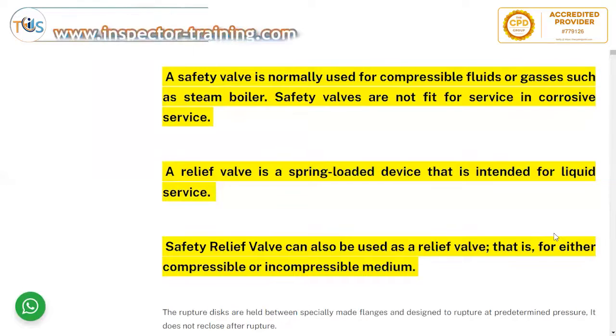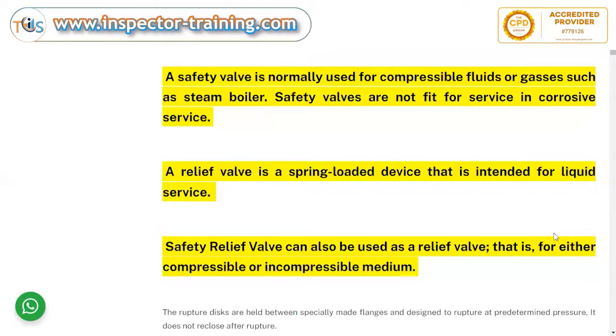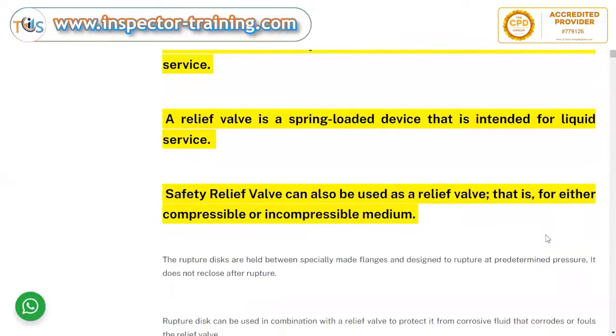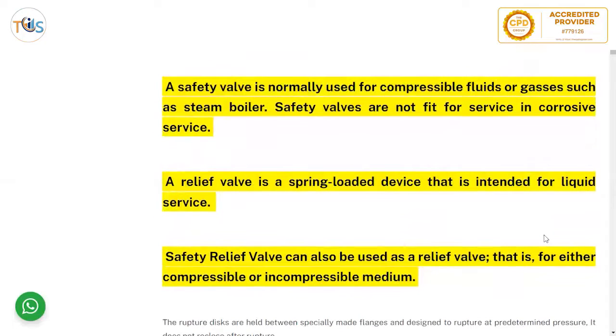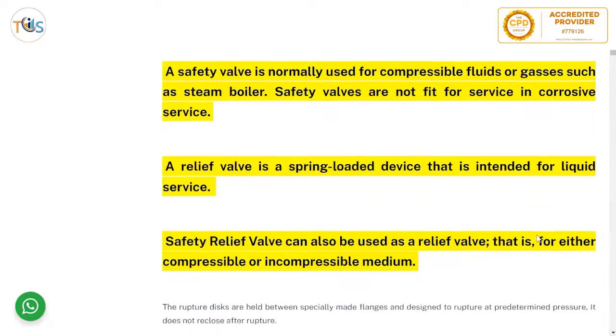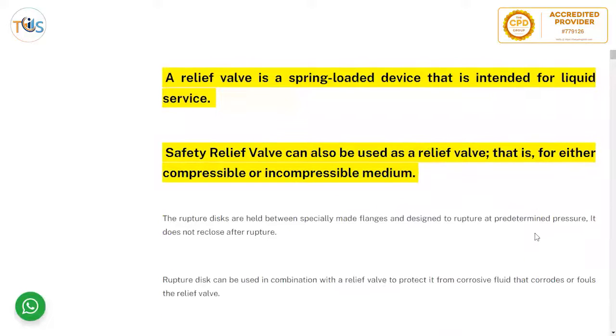A relief valve is a spring-loaded device intended for liquid service. A safety relief valve can be used as either a relief valve — for compressible or incompressible medium. This is a potential exam question: safety valve is for compressible (gas) service, relief valve is for incompressible (liquid) service, while a safety relief valve can be used either way.